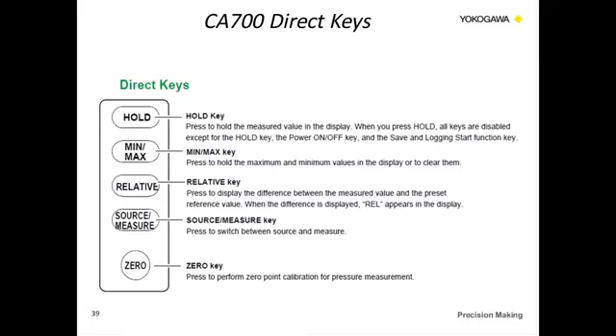The source and measure key, this is for the electrical measurements. You can switch between sourcing and measuring. And the zero key, this is, zero is the sensor within the unit. This is recommended before using the unit for any types of calibration. And also if you're going to change the orientation of the unit, move it from one different orientation to another, it's a good idea to go ahead and zero that out.